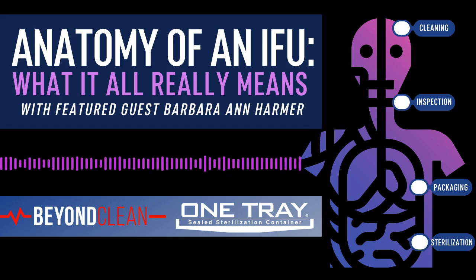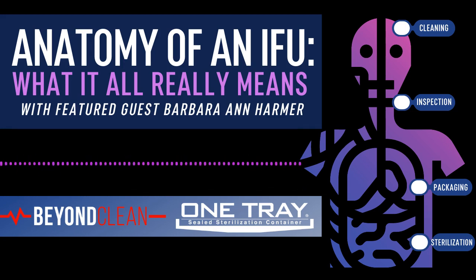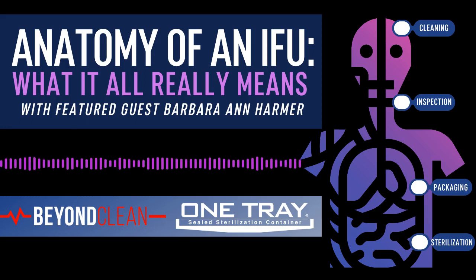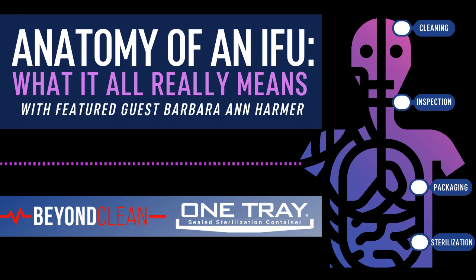Barbara, let's start with sterilization parameters. Can you talk about that? Absolutely. So the literature that we follow addresses sterilization parameters as the time and temperature requirements for the cycle chosen. This should, of course, be found in the IFU. You should be following these listed requirements in the medical device's IFU, but you could have 30 instruments, for example, in a tray. You'll need to follow and work through this maze to select the appropriate cycle, exposure time, and temperature. It's always not advisable to over-sterilize instruments or implants. The last item that is found in an IFU is the dry time, but you didn't hear me mention it as a sterilization parameter because it isn't. It is part of sterility maintenance. So again, when you look at the IFU, you've got sterilization parameters as well as sterility maintenance.